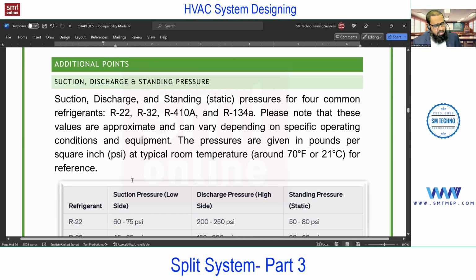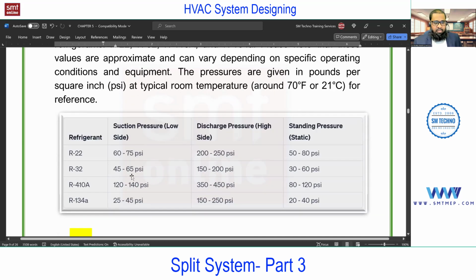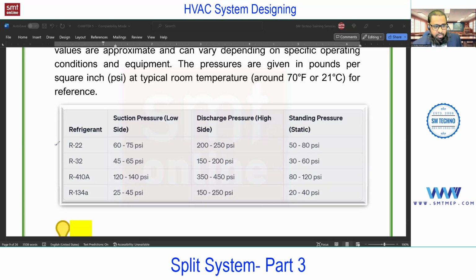So what are the suction, discharge, and standing pressures? You can relate this. Suction means what? Suction by which component? The compressor. So suction means the refrigerant flowing from indoor to outdoor, at low pressure and low temperature. Just for example, if I take R22, the suction side is 60 to 75 psi. Compared with this, discharge is higher. Discharge means after compression; the compressor is used to increase the pressure. So this is before compression, and this is after compression. 60 to 75 psi for R22, and the discharge pressure is between 200 to 250 psi after compression.